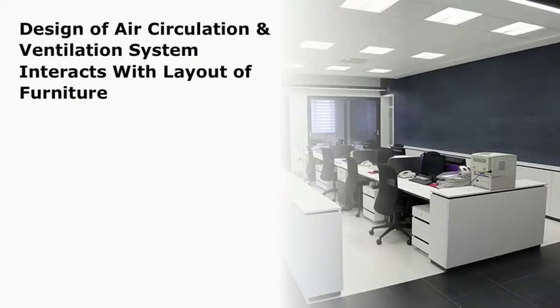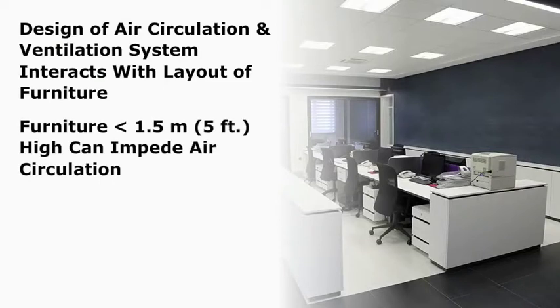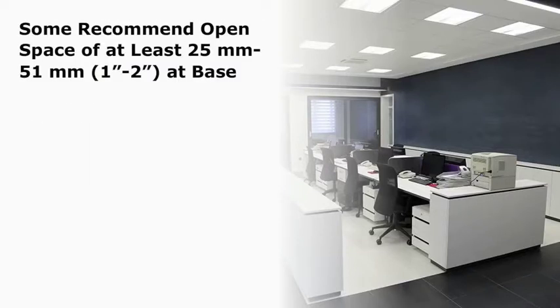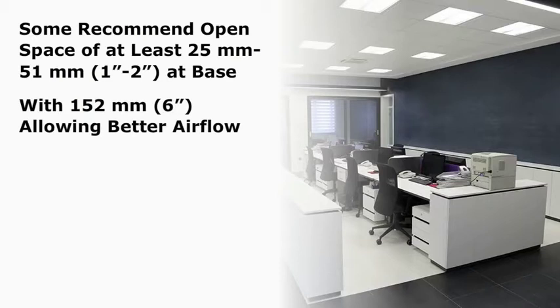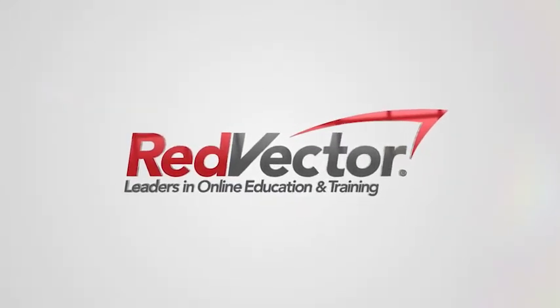The design of the air circulation and ventilation system interacts with the layout of the furniture. Even furniture like filing cabinets and acoustic screens less than 1.5 meters or 5 feet high can impede air circulation, especially if they extend to the floor. Some sources recommend an open space of at least 25 to 51 millimeters or 1 to 2 inches at the base, with 152 millimeters or 6 inches allowing even better airflow. If walls or full-height partitions enclose spaces, each enclosed space should have one supply vent and one return or exhaust vent.